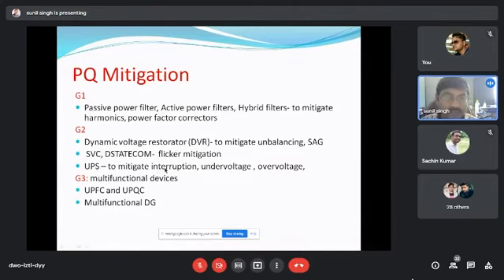It mitigates interruption. If there is a power cut, we can still have the power supply without any intervention. The computer keeps running. Under voltage, over voltage and all other problems are handled by an online UPS. Actually, UPS has three types: online UPS, offline UPS, and hybrid UPS. Online UPS is the most important from the power quality point of view.